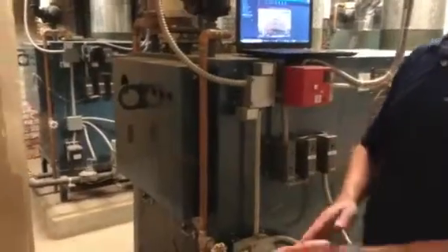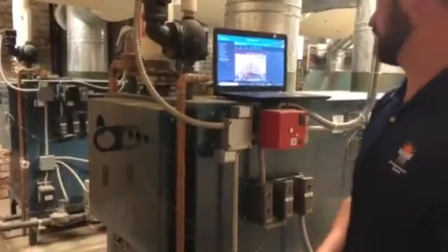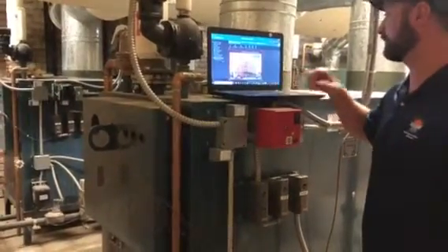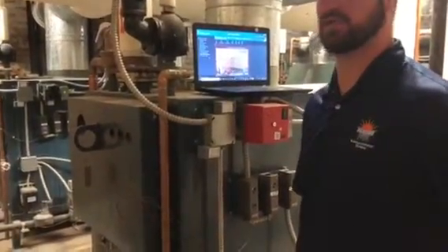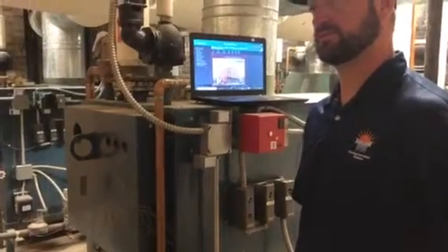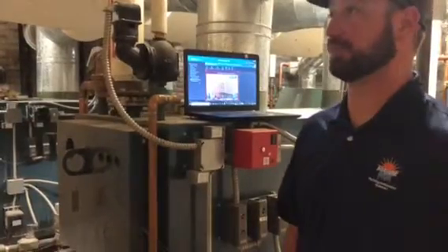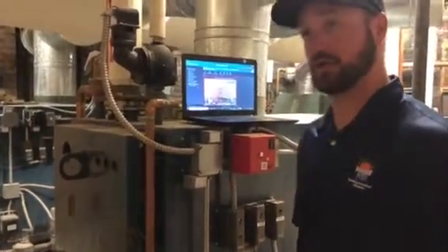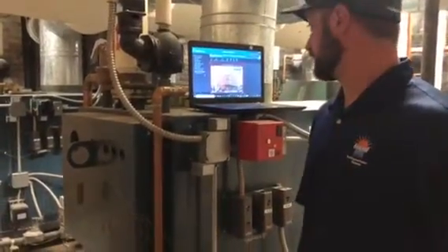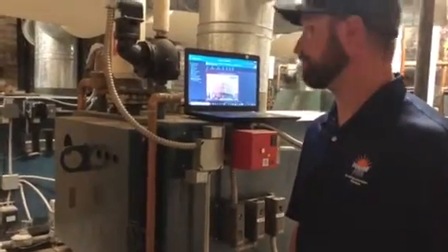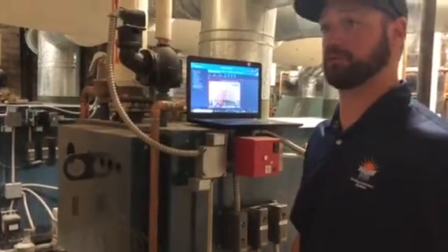Now, is this a full glycol system? I believe so, we didn't open it up. I do believe it is glycol. So there's no auto feed or anything like that for the glycol? I don't believe so, I haven't seen anything. Now, will it monitor the level of the glycol? No. Nope, if there's a leak or something, then we'll probably get a boiler failure. Right. Low water cutoff will lock this guy out. So it would actually have to drop below a certain level before the boiler would shut off. Yeah, and then they would have to put more glycol. I'm sure somebody would notice the leak before that.